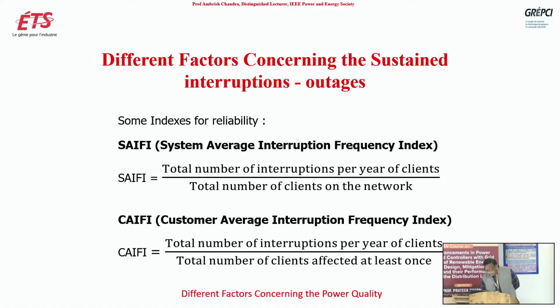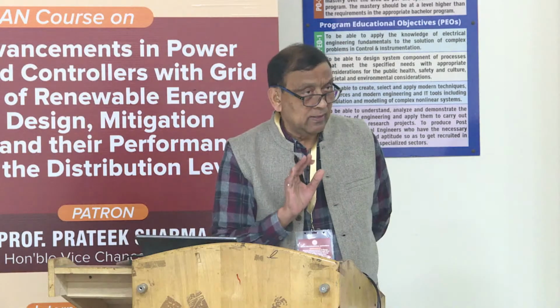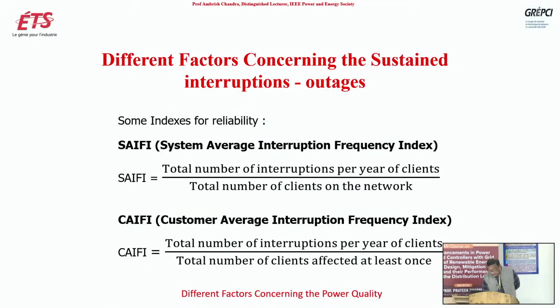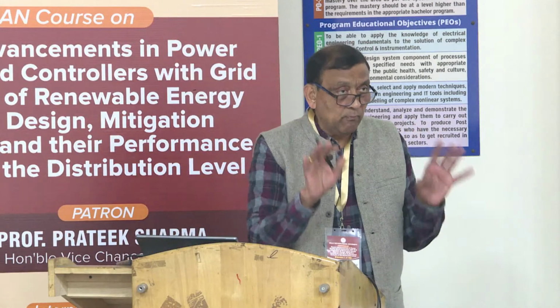And what is CAIFI? Customer Average Interruption Frequency Index. SAIFI is the system average; here it is the customer average. So total number of interruptions per year divided by total number of clients affected at least once. In SAIFI you don't care if certain clients are affected, but here it is clients affected at least once. So suppose 30 outages were there and only 5 clients were affected. So CAIFI will be 6. If SAIFI equals CAIFI, it means all the customers were affected the same way. But if CAIFI is much more than SAIFI, like here, 6, it means certain customers were affected more than other customers.